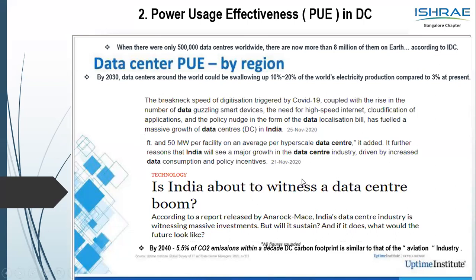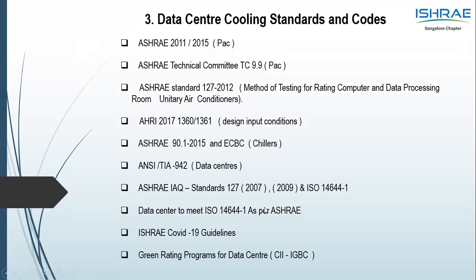We saw it last year as we talked. Even this year, there is a boom in data centers within India. So coming back to the cooling, in the PUE, what we noticed is 30% of the cooling goes into the PUE. These are the standard codes which I picked up by reading various articles on data centers. I've just summarized these for you. You can take a quick snapshot of this, all related to data center cooling.